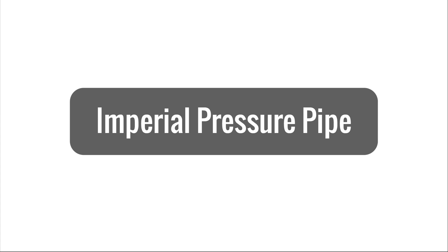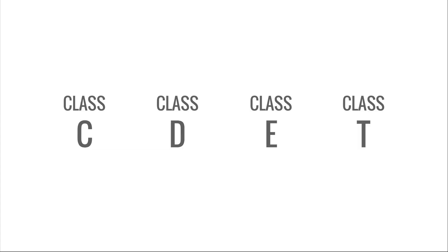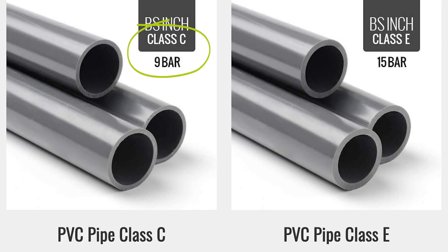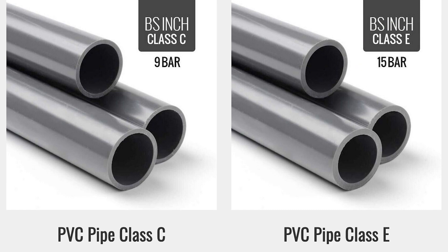Now let's take a look at imperial pipe. Imperial pressure pipe is organized into classes. The common classes you will see are Class C and Class E. Each class will have a pressure rating associated with it. For example, a Class C pressure pipe has a rating of 9 bars and Class E has a rating of 15 bars. You can see that the Class E pipe has an increased wall thickness when compared to Class C.